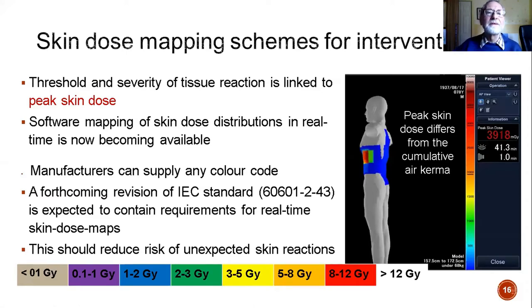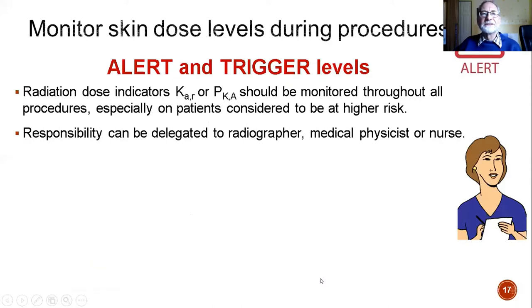There are now being developed skin dose mapping software for mapping skin dose distributions. Manufacturers can supply any color code, but a forthcoming revision of the IEC standard is expected to contain requirements for real-time skin dose maps. This, hopefully in the future, should reduce the risk of unexpected skin reactions. The colors at the bottom give an indication of what might be used as colors.